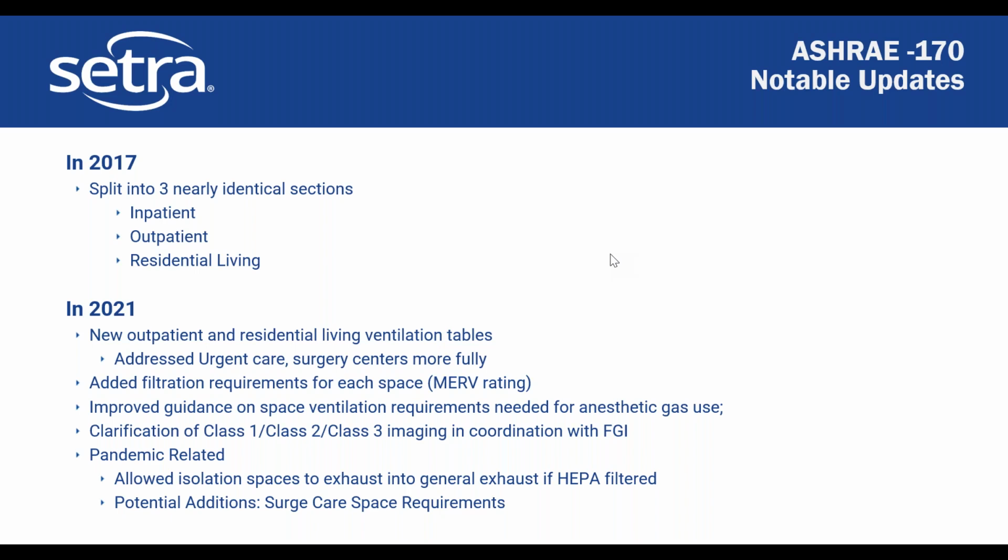But the one change they made to the spec to address that was they're now allowing isolation spaces to exhaust into your general exhaust system. In the past, any isolation space had to exhaust individually or 100% outside. So in certain cases, you now can do this as long as it's HEPA filtered. This was to make it so that you could have more isolation spaces in a hospital.